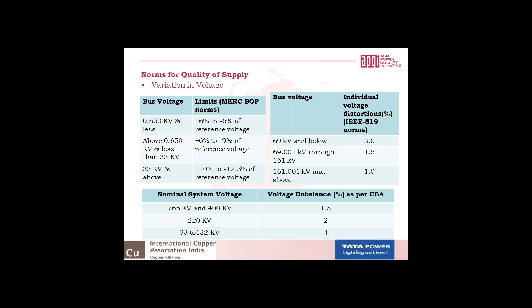Now, if you compare these norms with the IEEE guidelines related to bus voltage, you will find that for voltages up to 69 kV, the permitted band is 3%. For voltages between 69 kV to 161 kV, the permitted band is 1.5%. And for 161 kV and above, the permitted band is 1%. If you see the CEA, or Central Electricity Authority, guidelines for voltage unbalance, for systems between 400 kV to 765 kV, the permitted unbalance is 1.5%. For 220 kV systems, it is 2%. And for systems between 33 kV to 132 kV, the permitted voltage unbalance as per the CEA guidelines is 4%.